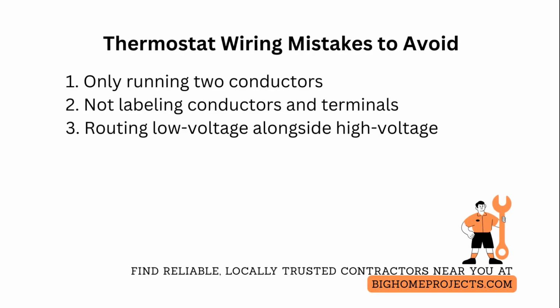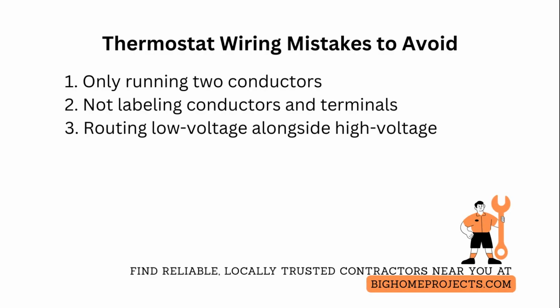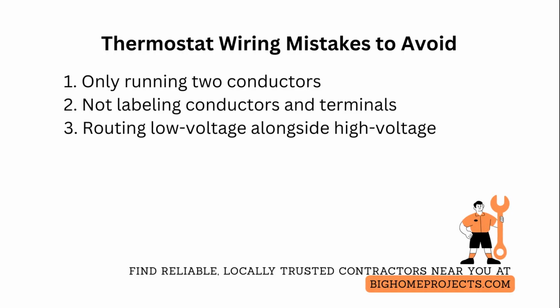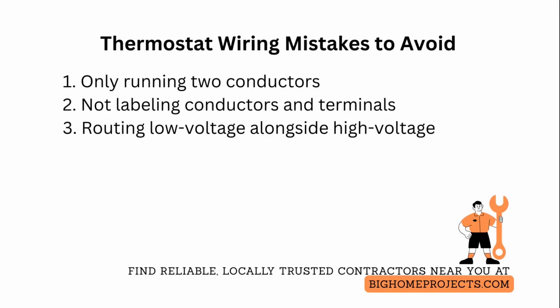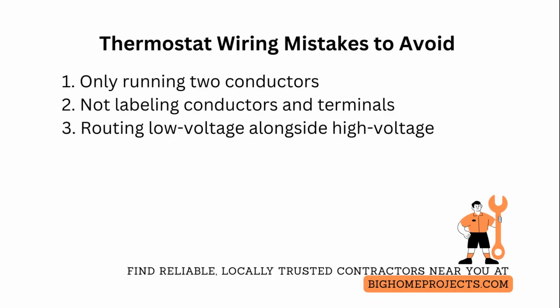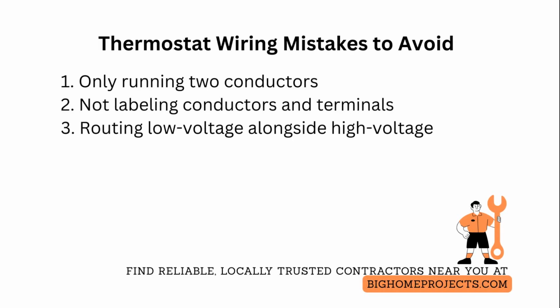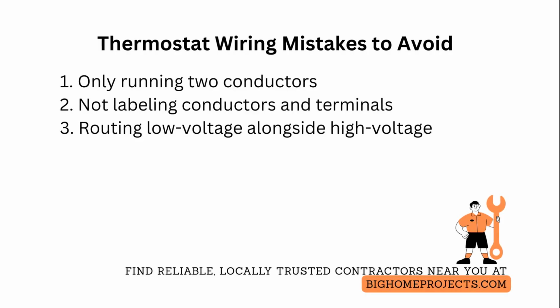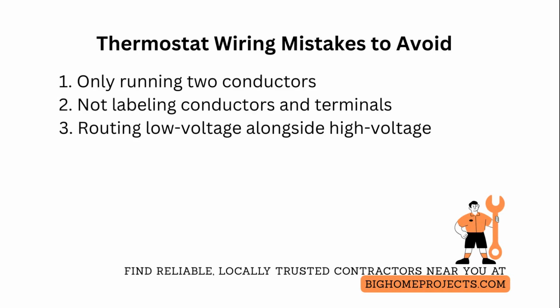One of the top problems is failing to label conductors and terminals, which makes troubleshooting long and costly. Fix that by using permanent, clear labels at both ends and keeping a wiring diagram photo with the equipment. Another frequent issue is routing low-voltage thermostat wiring alongside high-voltage mains, which causes noise and intermittent control issues. Fix this by maintaining separation, using shielded cable if unavoidable, and grounding shields properly.